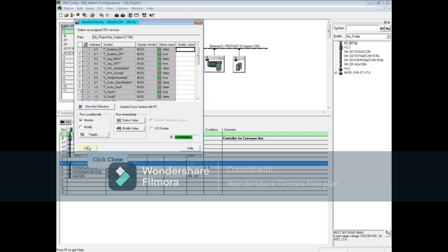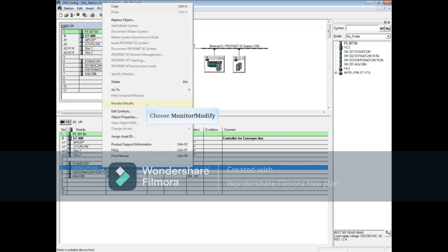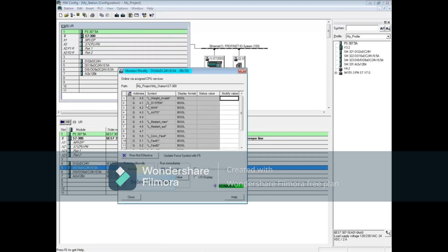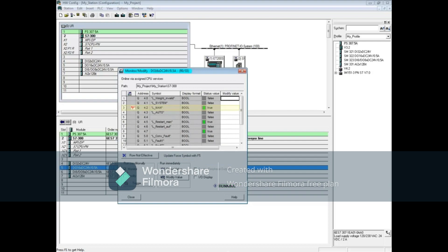Right-click the digital output module, choose monitor/modify again, and put a check in the monitor box. To see if any forces are taking place, press the F5 key. Line 3 Q4.2 is being forced from a force table, as indicated by the red F.